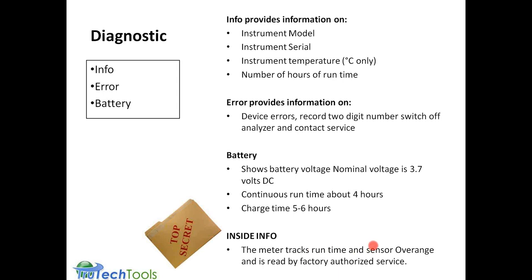It also has a sensor overrange feature that can be read by factory authorized service to tell if the sensor has gone into overrange. Unfortunately, if you overrange your sensor too much, you can damage it, and because it was a willful act to overrange it, most of the time it won't be covered by warranty. Question I got here: can the meter be operated when charging? The answer is yes.